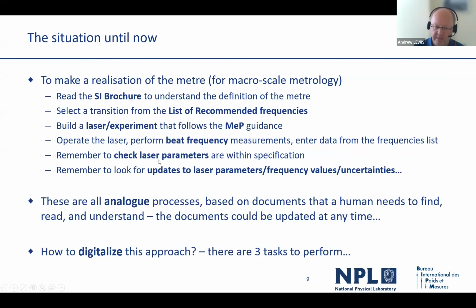Of course, you'll be checking to make sure that your laser is operating within specifications all the time. And in between doing calibrations for customers, you will also be checking to make sure that the values you've read from this PDF document haven't been changed. Now, the CIPM does occasionally change the values in the document when more data is made available. Sometimes they relax the parameters, sometimes they tighten them up and make small adjustments to the frequencies. And you really ought to be checking to make sure that you're using the most up-to-date data all of the time.